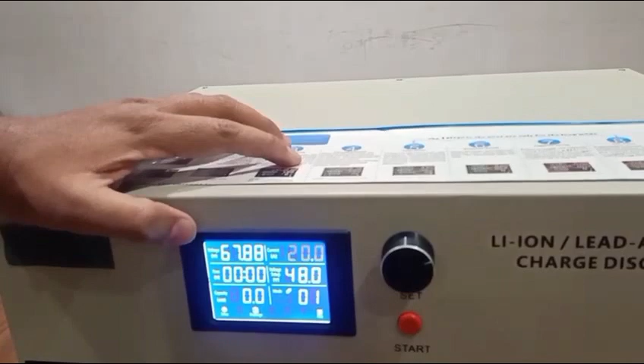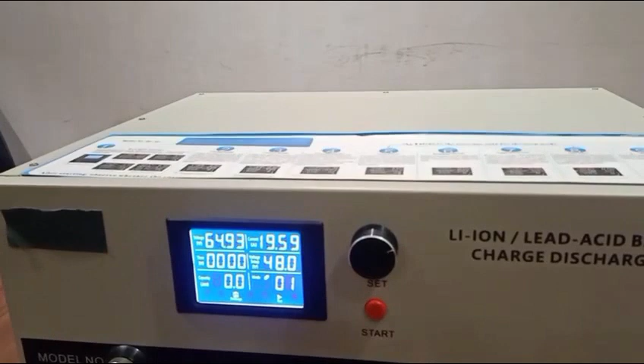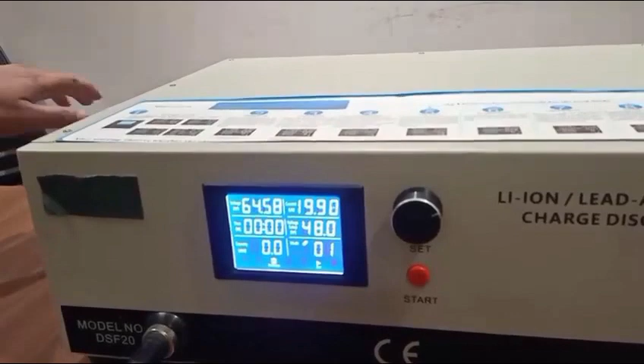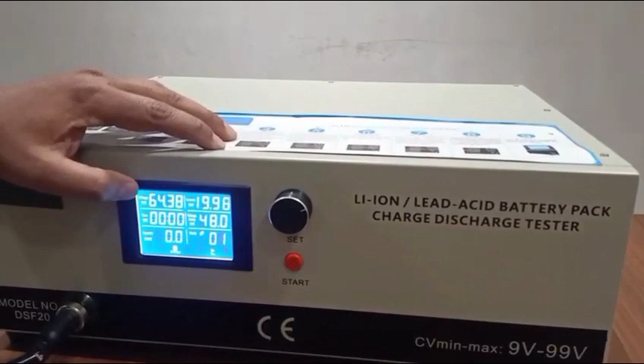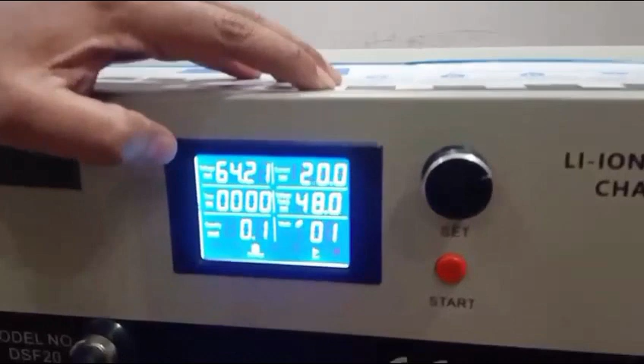As you press the start button, you can hear the sound of the fans. Currently this machine is running and it is discharging the battery pack, and that's why you can see the decrement in the voltage here, 64.32, and it is getting down and down, and the constant current it is taking from the battery pack is around 20 ampere.